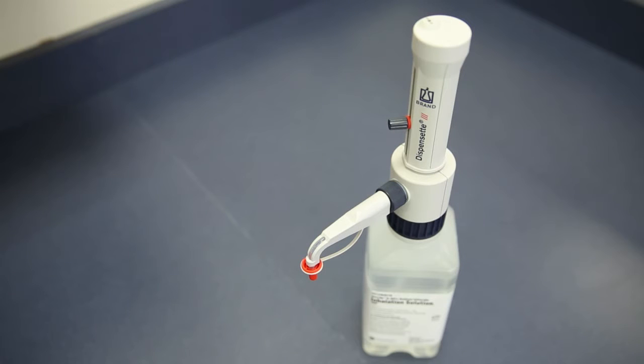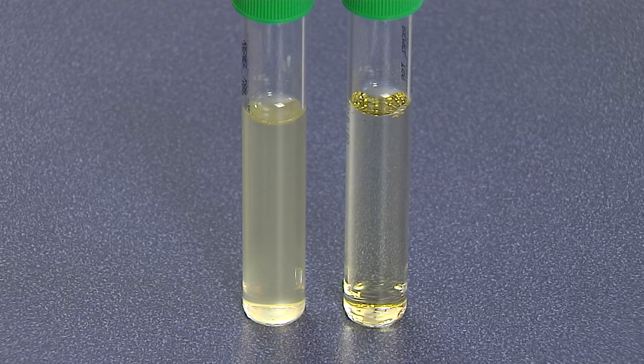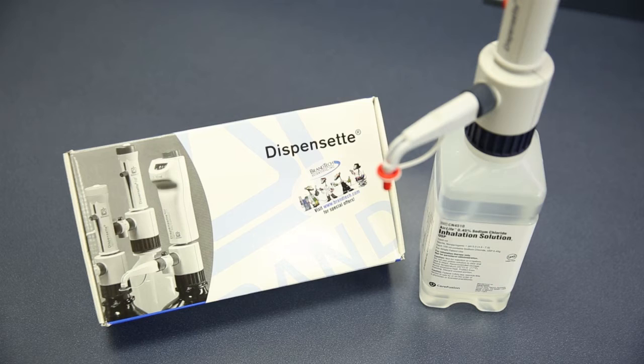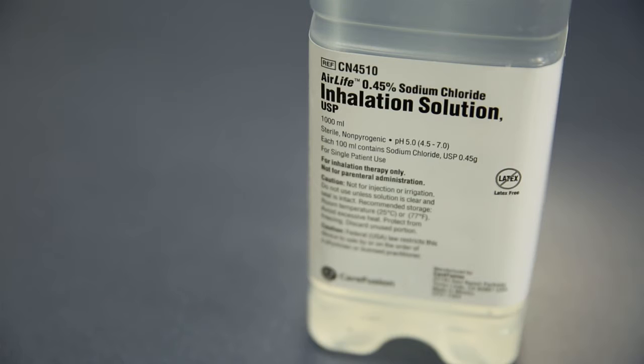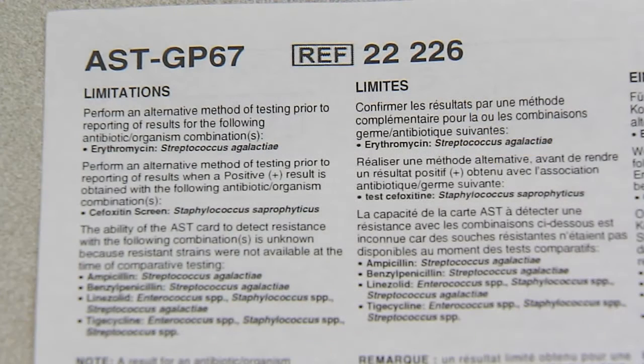Saline sterility and pH. Has the saline been stored properly and tested weekly for sterility? If using a Dispensette, has it been properly maintained according to manufacturer's guidelines? The saline pH should be between 4.5 and 7.0. If necessary, verify the pH periodically. If the test has been performed correctly, consider these additional items.